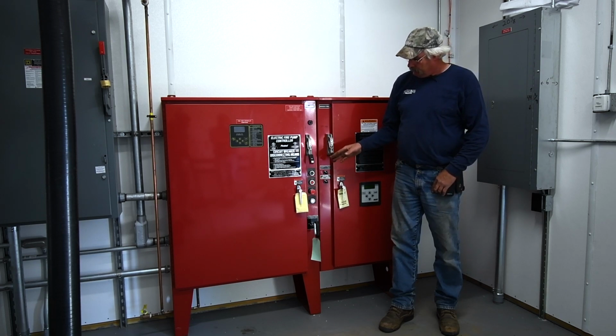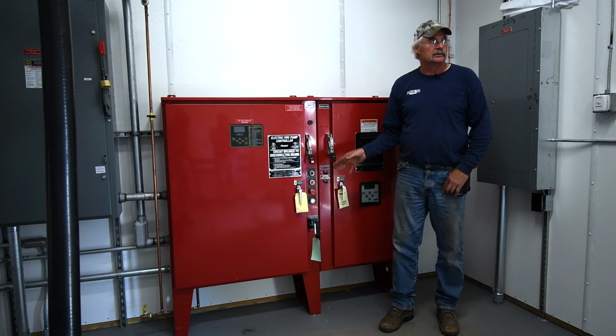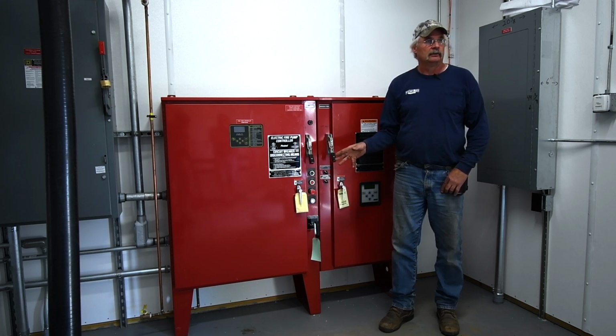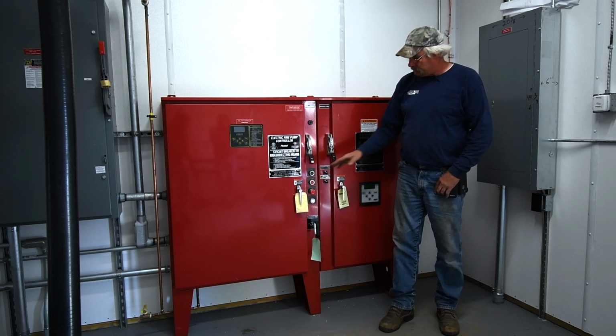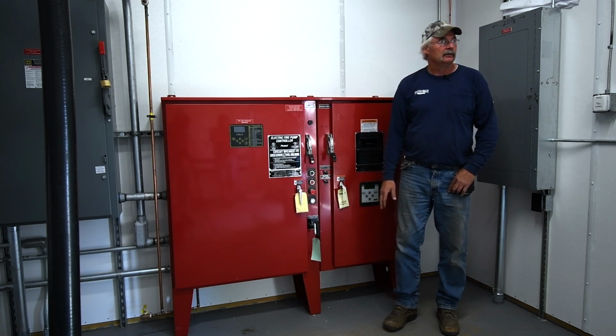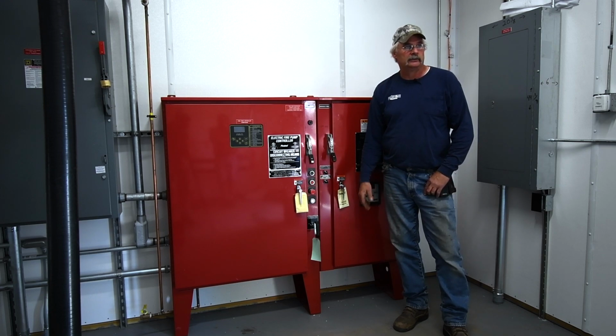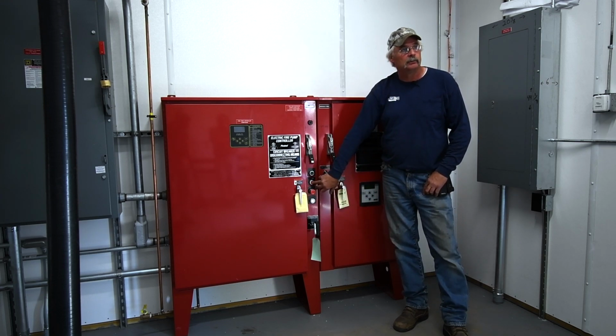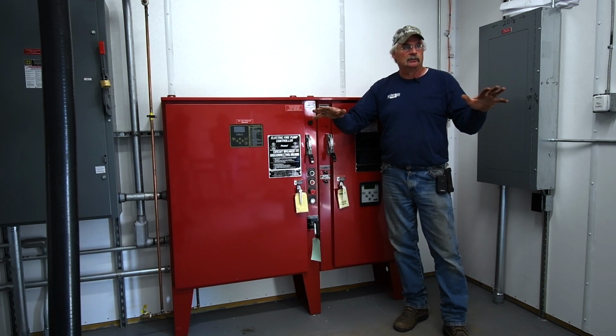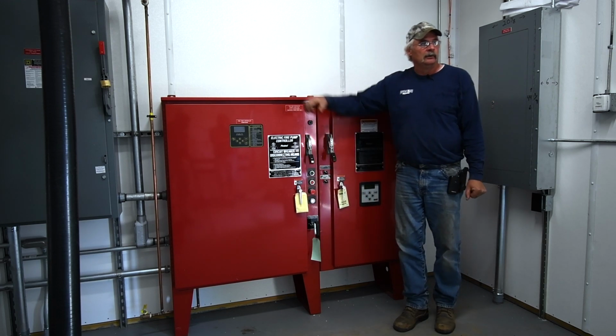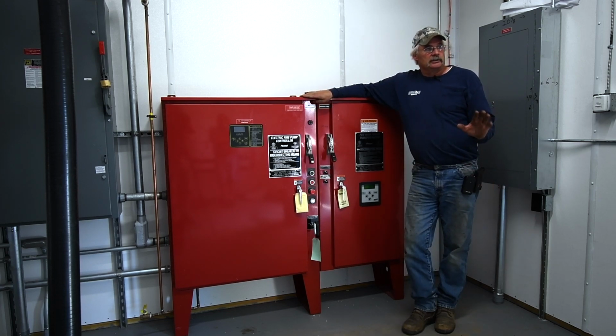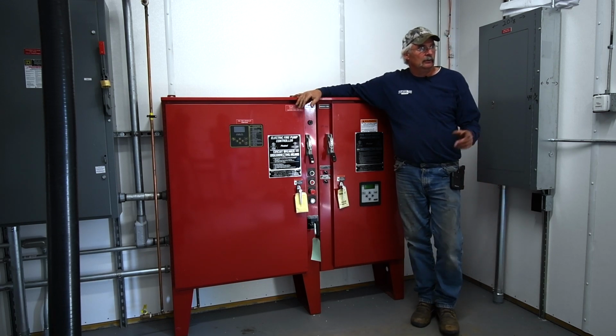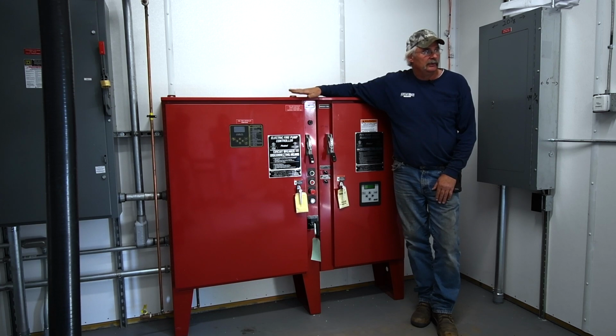Anytime that you're using this fire protection equipment, just please keep in mind that it's fully automatic. So if you hit a start button accidentally and you say, geez, what can I do? It's set up on a timer. You can come over here, hit the red button, hit stop. Once the pressure's up, the system will just maintain itself and shut right back off. Any questions? There's stickers on everything. Call the 24-hour service. If you have just a question, like what about if I did this or that, call up and ask first, but make sure you contact the local authority having jurisdiction on this stuff before you do any work on it.